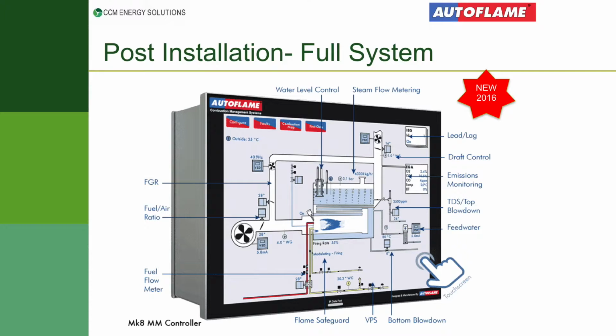And this, as I said, does everything on the boiler. You get rid of all the PLCs, you get rid of all the individual controllers in your panel, and everything is done through this unit. As I said at the start, the system started out in the 80s as a fuel air ratio controller. So here we're measuring our air damper and our gas valve or oil valve here. And we fine tune that. We tell exactly how much gas and exactly how much air is needed at every point from high to low fire. We can add additional controls, flue gas recirculation, stack damper controls, atomizing valves for oil.